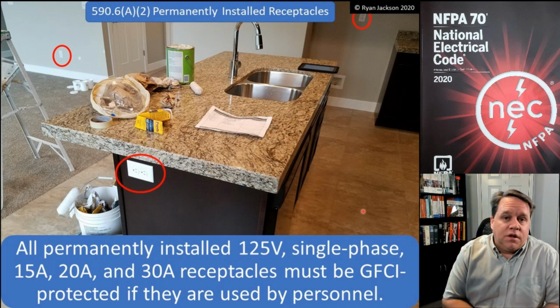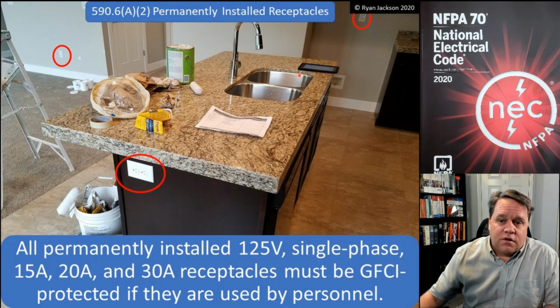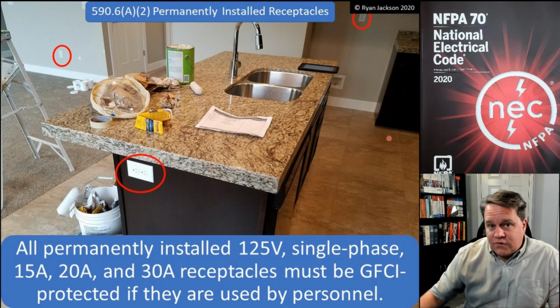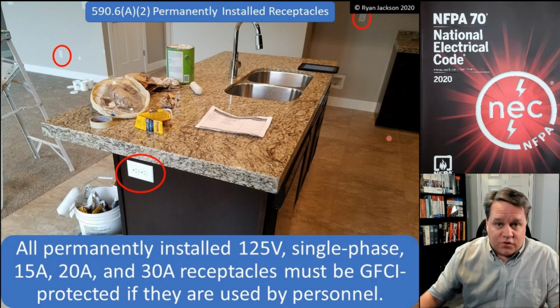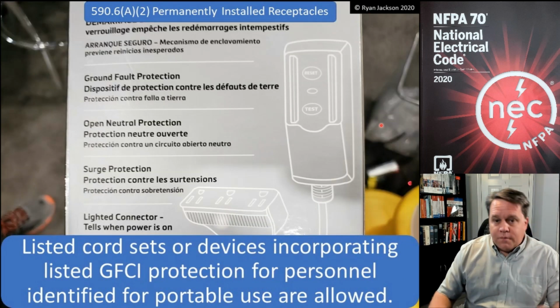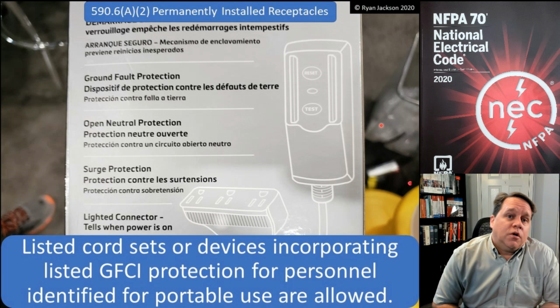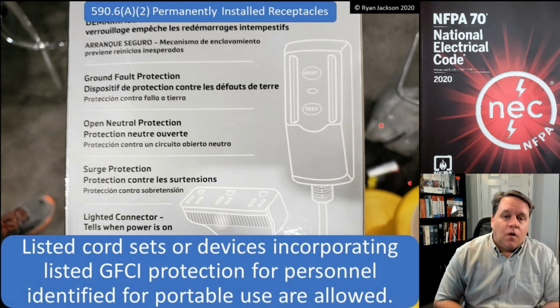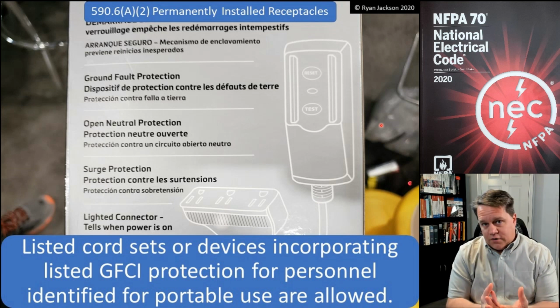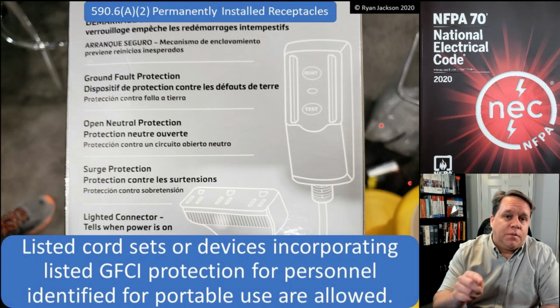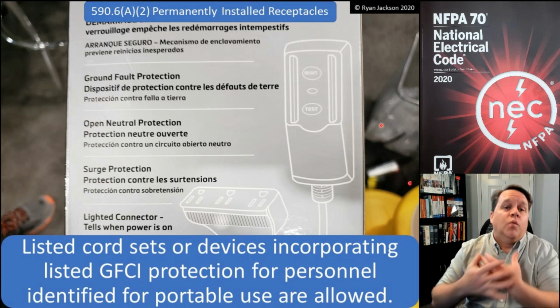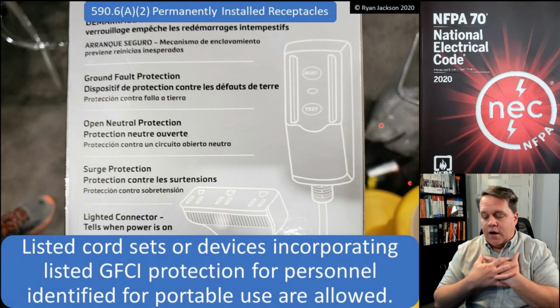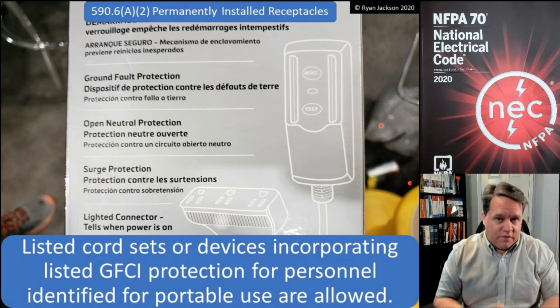So maybe you can leave a note and say, look, the receptacles in the kitchens and bathrooms, you can use those for construction. Or maybe you read this part of the code and you put it into your contract and you say, listen, receptacles that are permanently installed, GFCI protection is to be provided by the individual contractors. We will provide temporary power for receptacles that are not part of the building.